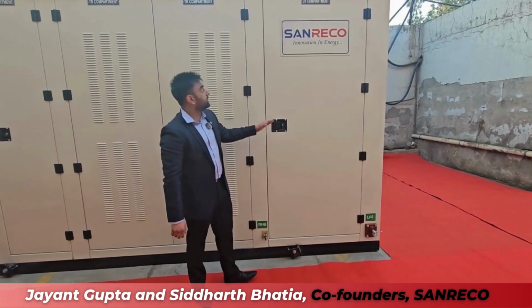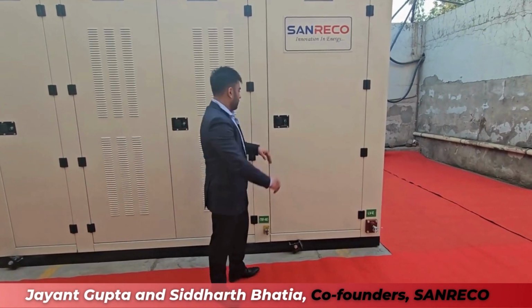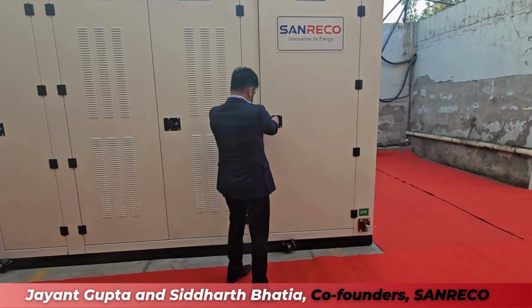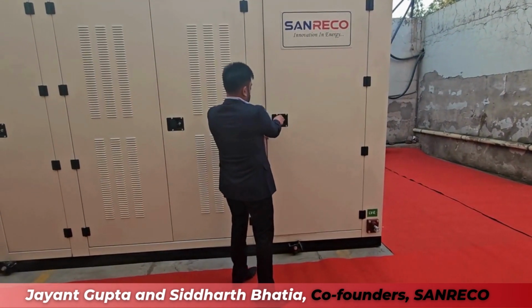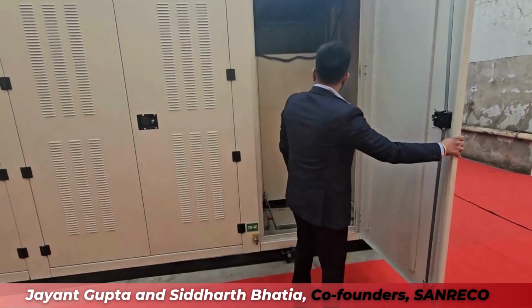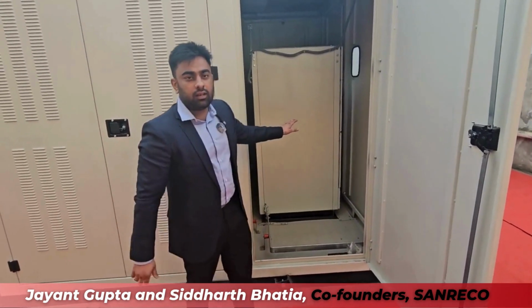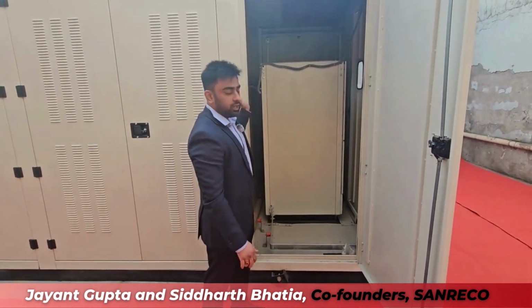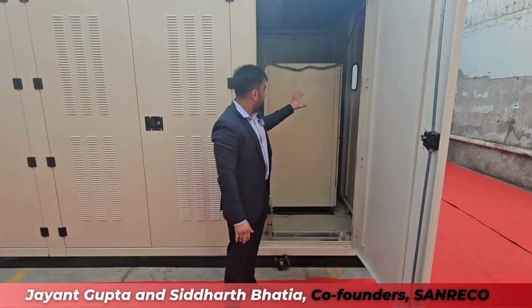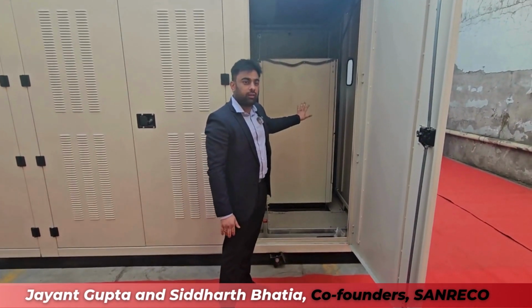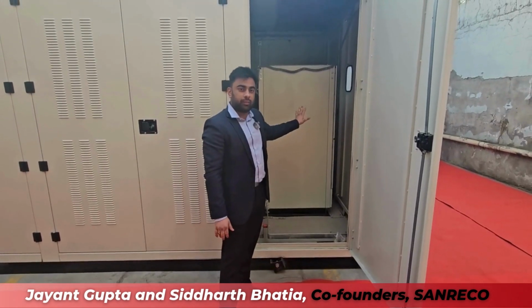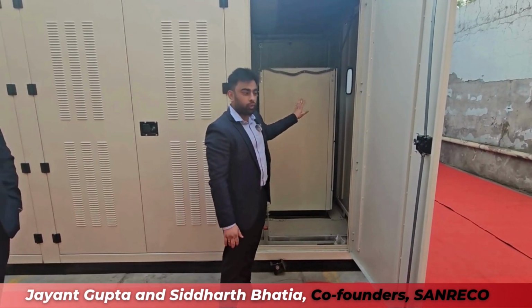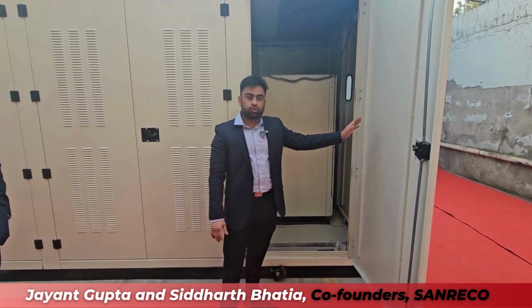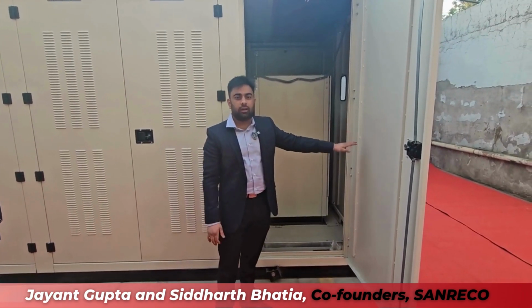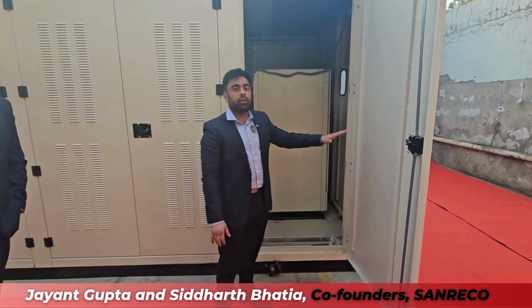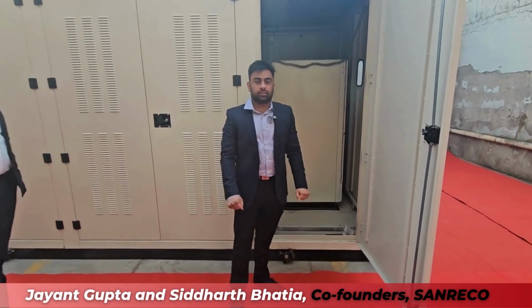Now we come to the third section, the LT compartment. Here we have the LT panel. From the transformer comes 400 volts, and there is an LT breaker, here an ABB make breaker. This is the LT panel from where the power goes to the complete plant, building, or area. This completes the CSS.